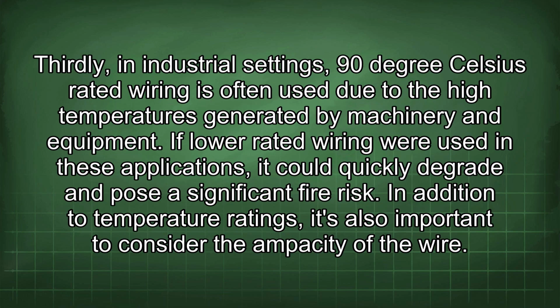Thirdly, in industrial settings, 90 degrees Celsius rated wiring is often used due to the high temperatures generated by machinery and equipment. If lower rated wiring were used in these applications, it could quickly degrade and pose a significant fire risk. In addition to temperature ratings, it's also important to consider the ampacity of the wire.